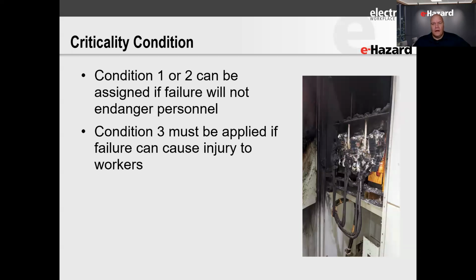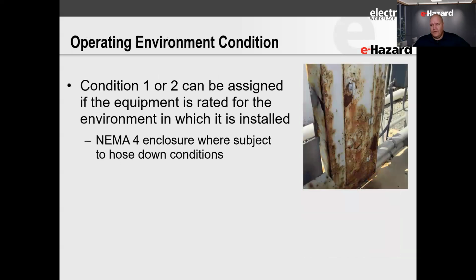The last condition we'll talk about is what we call operating environment condition. This is basically whether the equipment is rated to be installed in the environment it was put in. You see the picture here on screen—this was a NEMA 1 panel board right next to a cooling tower with all the different corrosive elements inside, and it's also outdoors. This is not rated for that environment, and you can see the result.